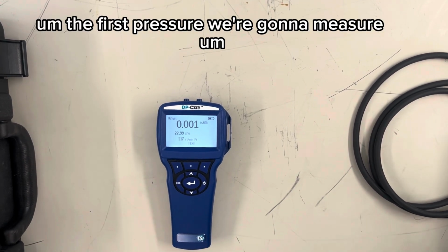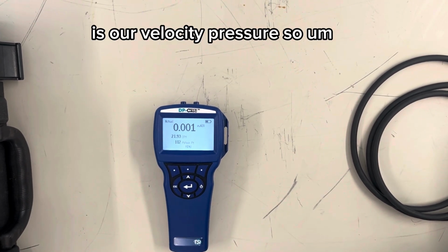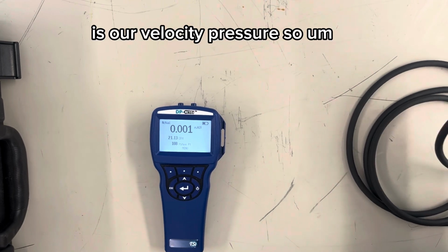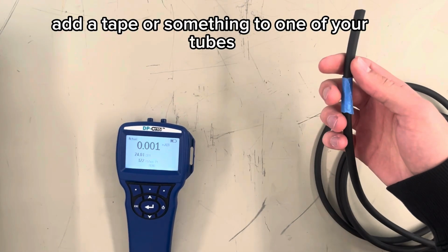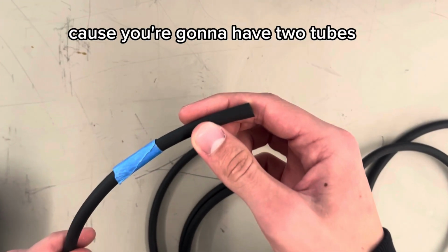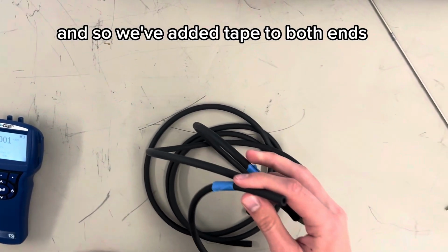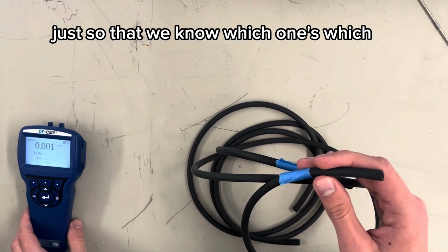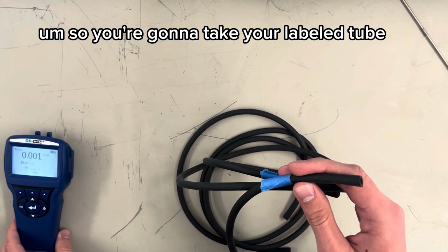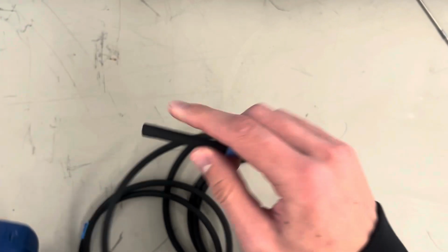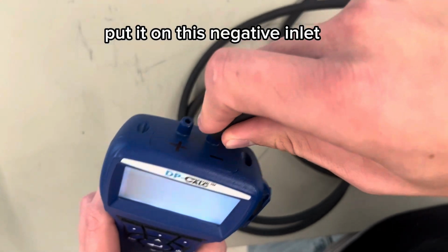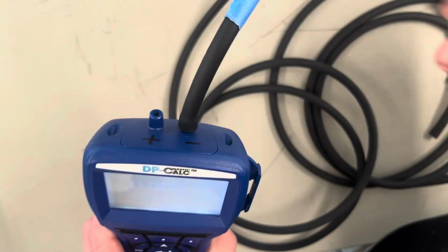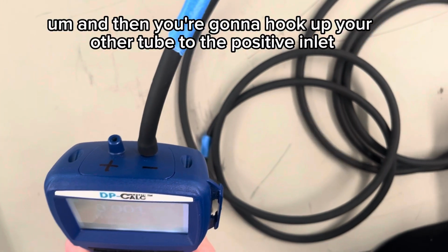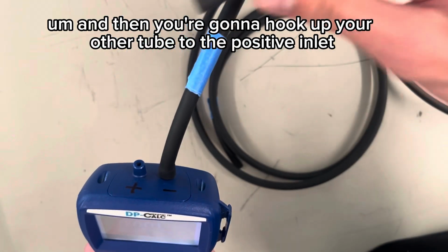The first pressure we're going to measure is our velocity pressure. Another good practice: add tape or something to one of your tubes, because you're going to have two tubes that you have to keep track of at both ends. We've added tape to both ends just so that we know which one's which. You're going to take your labeled tube, put it on this negative inlet, and then hook up your other tube to the positive inlet.